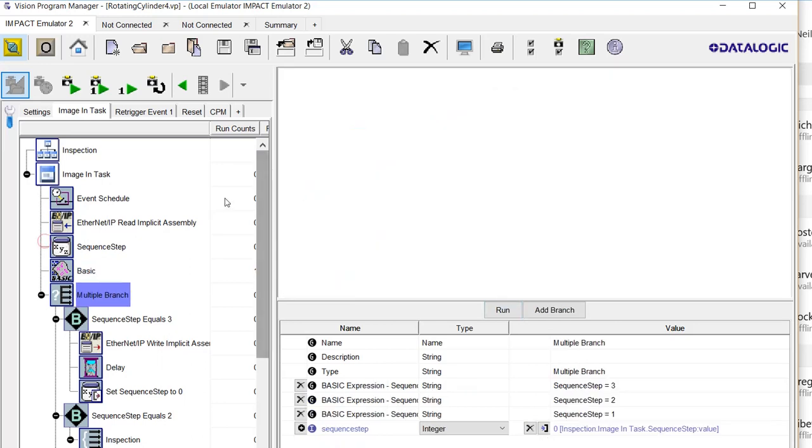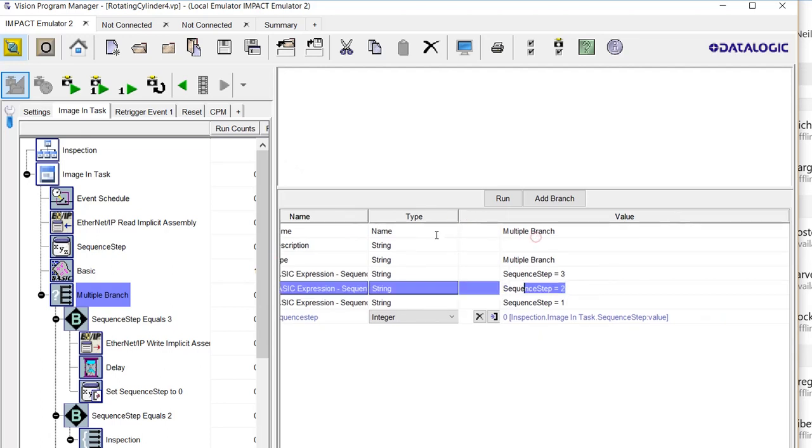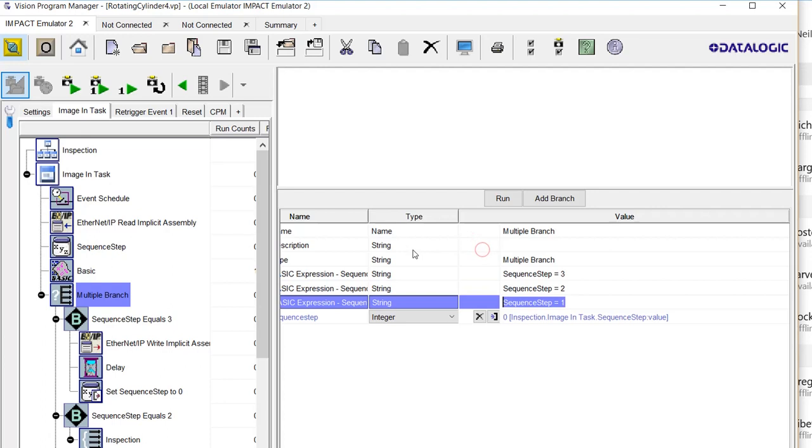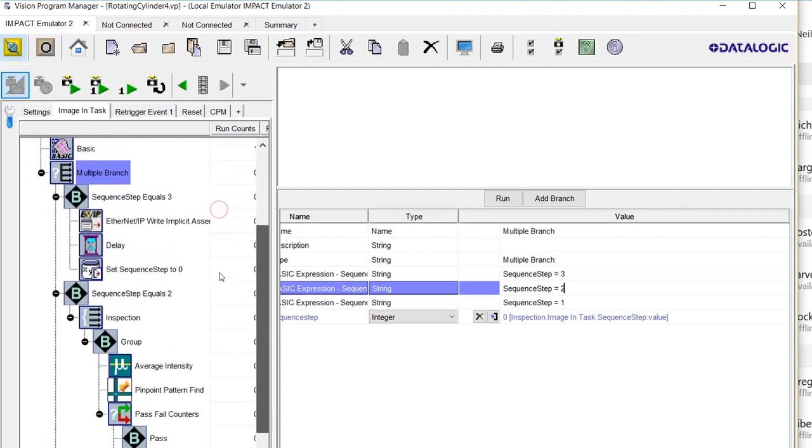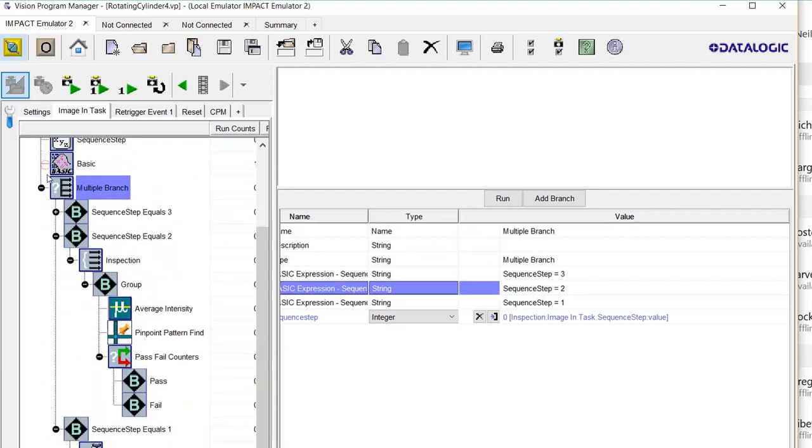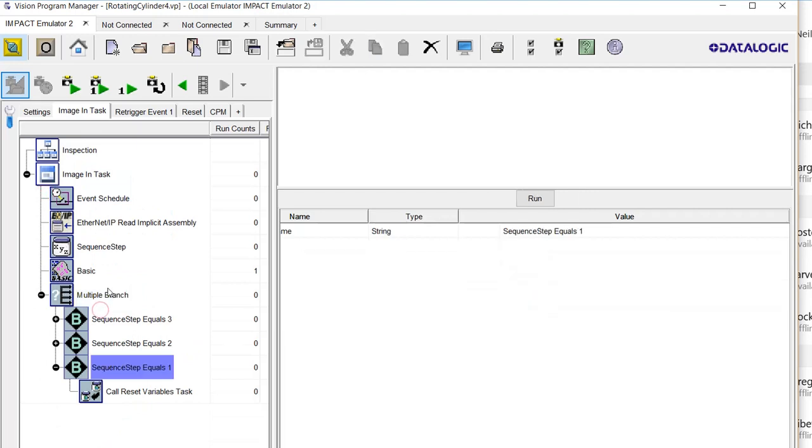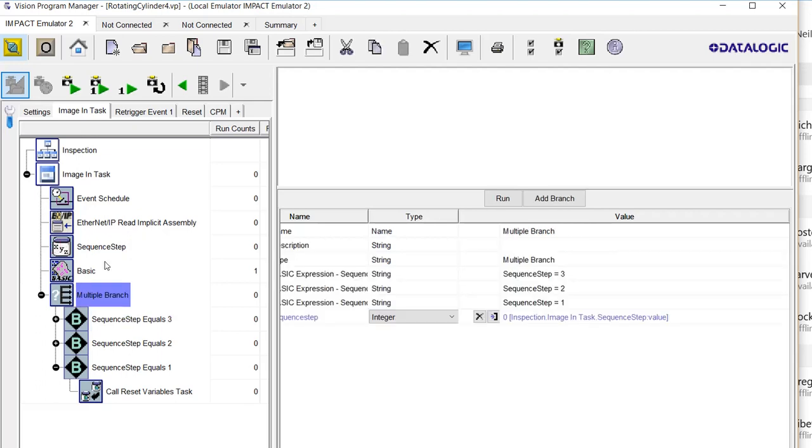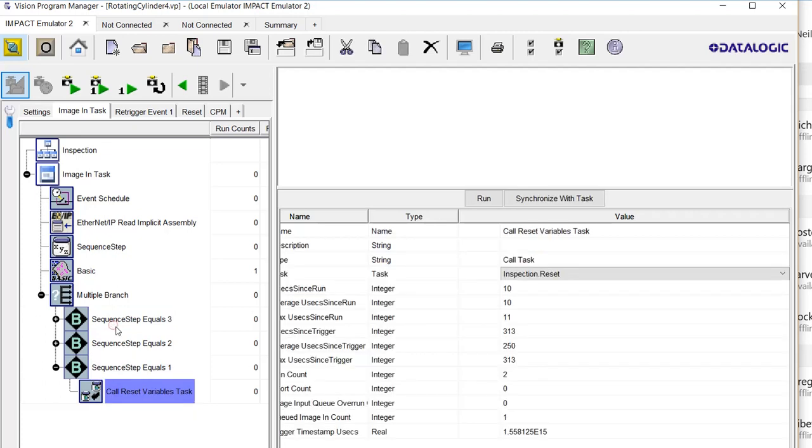This multiple branch instruction has three different basic expressions that's looking for this data instance called sequence step to equal 1, 2, or 3. And you can see here the multiple branches for it are 1, 2, and 3. They're in that order because the multiple branch instruction, as soon as it comes to the first true statement, it won't execute any others. Step 1 calls the reset variable task that we looked at earlier.